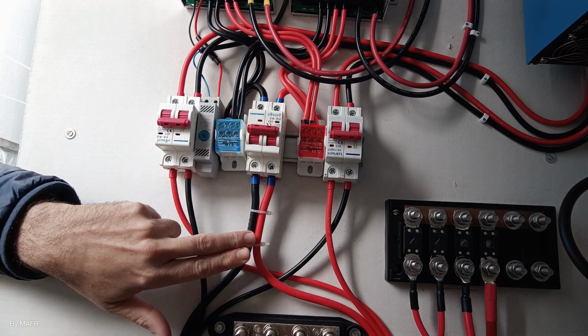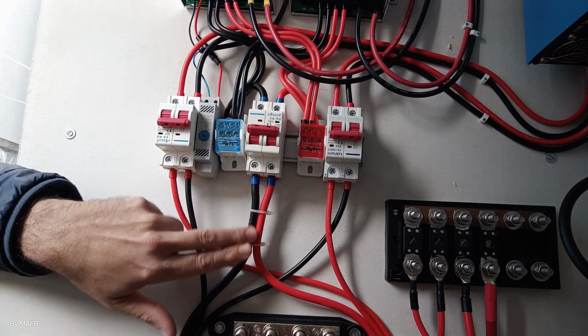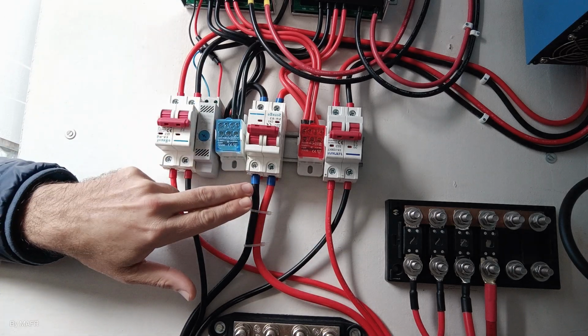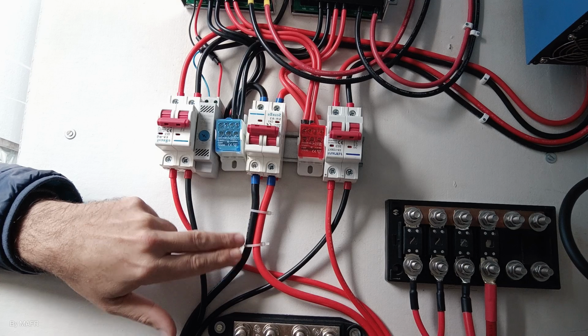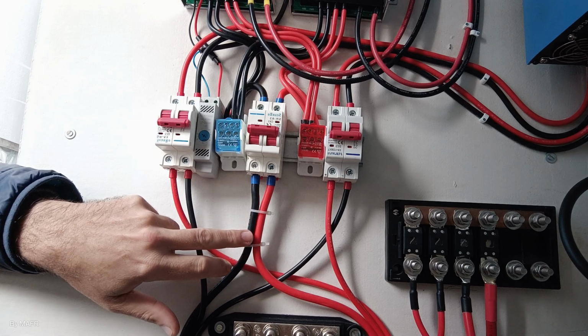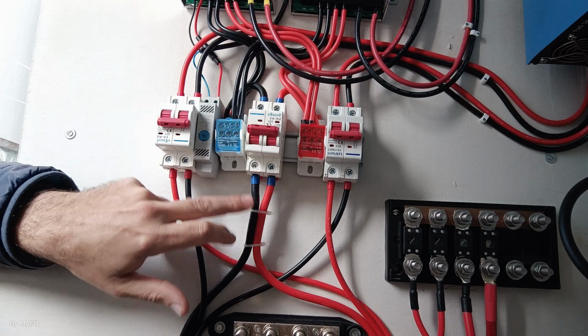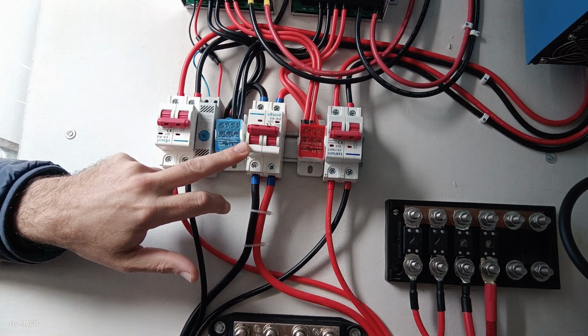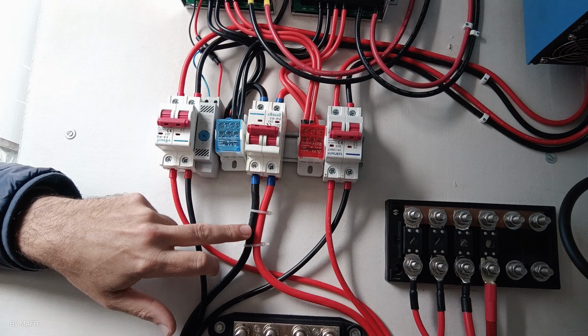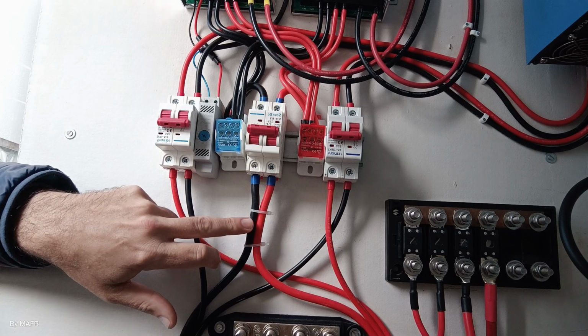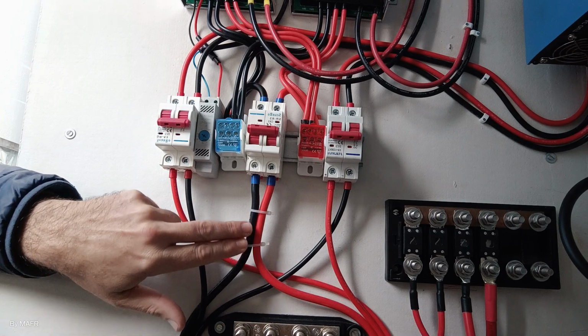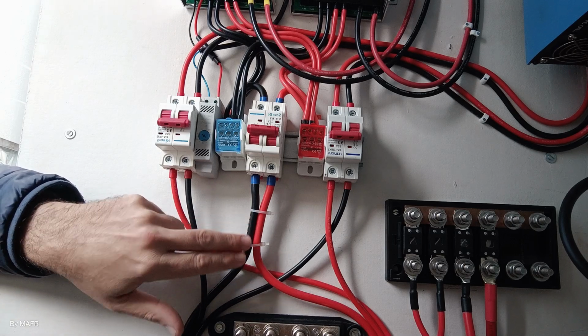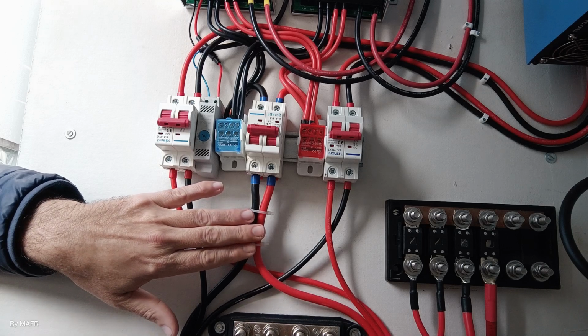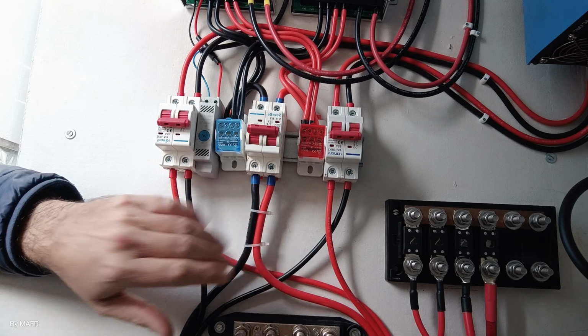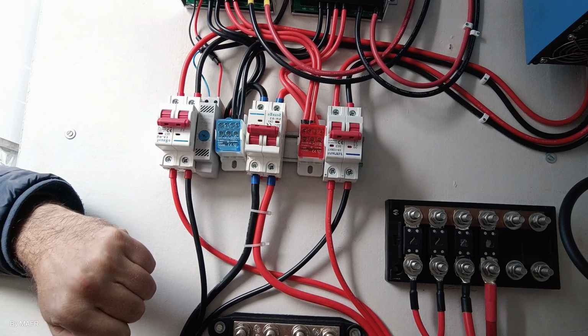And the main circuit breaker that gets the power from the charge controllers, I have a 6 AWG cable. That's because the maximum I can get here is 50 amperes, and this cable can manage around 93 amperes. Another important thing about all these cables is that they are flexible cables, because it's much easier to work with and much safer, right? So that's very important.